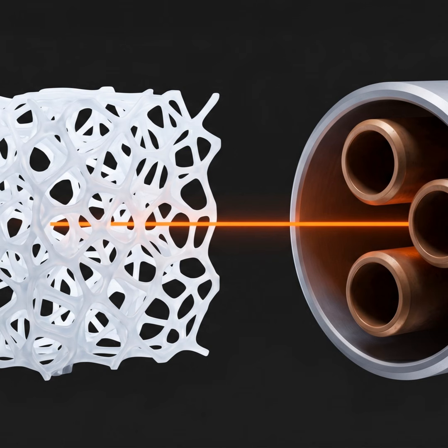The desuperheater. Okay, how does it work? It is the physical manifestation of restorative engineering. You basically install a specific type of heat exchanger directly on the discharge line. So you're catching it in transit. Exactly. You catch the hot gas after it leaves the compressor, but before it travels all the way up to the condenser on the roof.